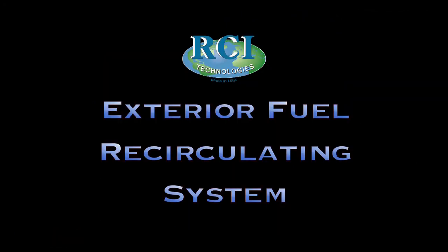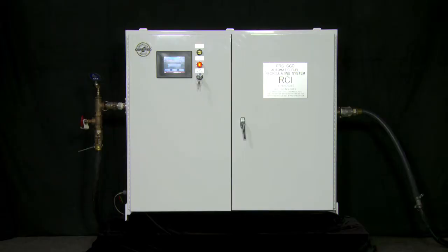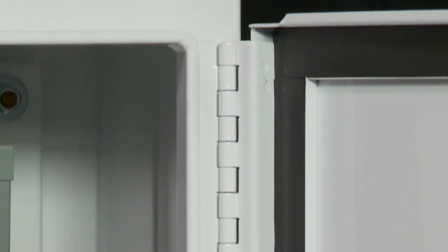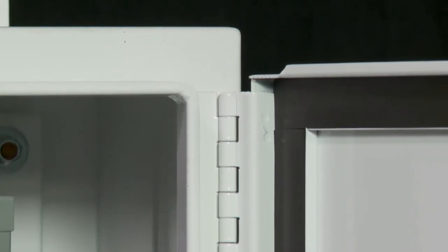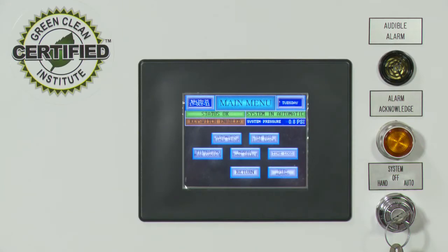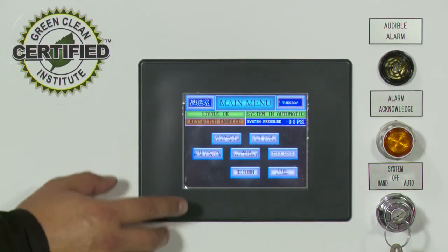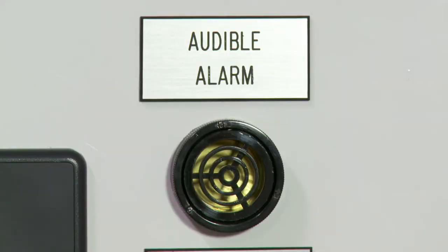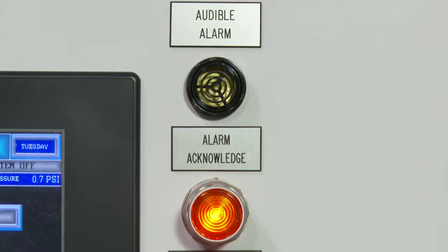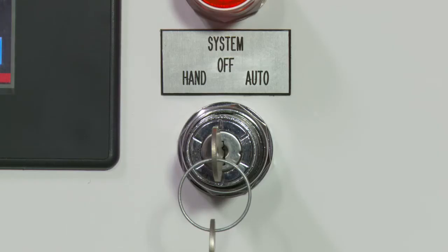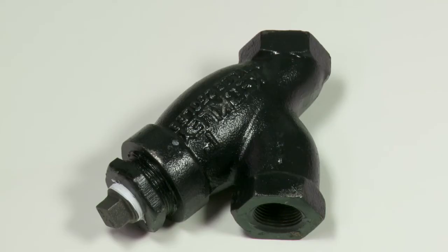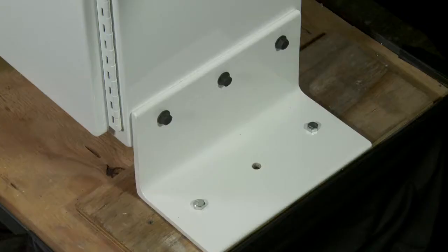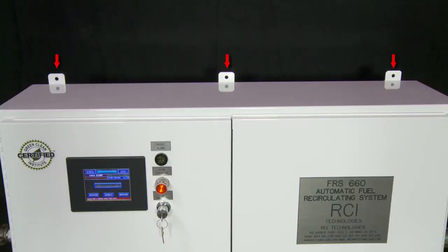And now, the exterior of the fuel recirculating system. The exterior of the standard 11 gallons per minute FRS comes equipped with a NEMA 4 rated system enclosure with hinged doors and industrial powder coating, a UL listed touchscreen display for system status and security enabled programming, a UL listed audible alarm, a UL listed visual alarm with reset button, a UL listed operator interface HOA switch, one 1-inch Y strainer, a handle with keyed lock, floor mounting feet, and wall mounting tabs.